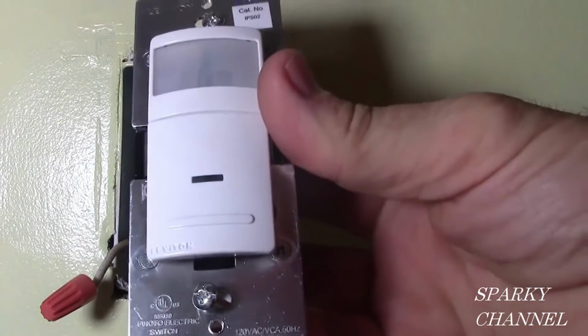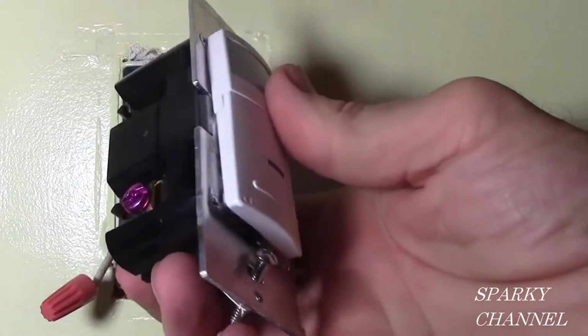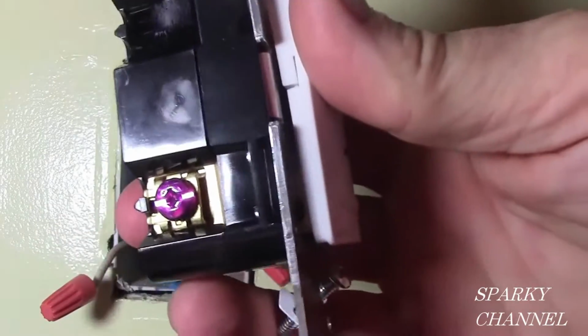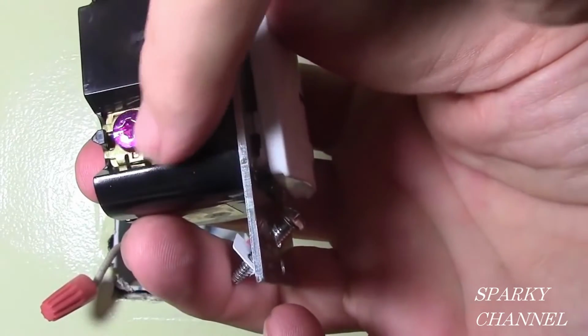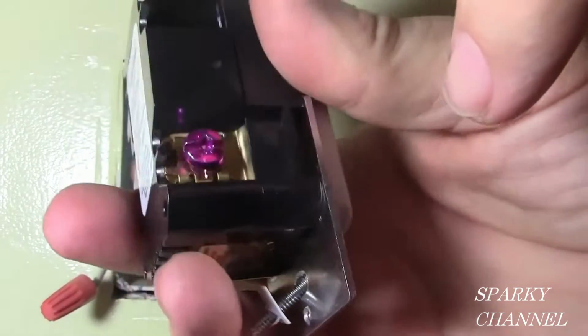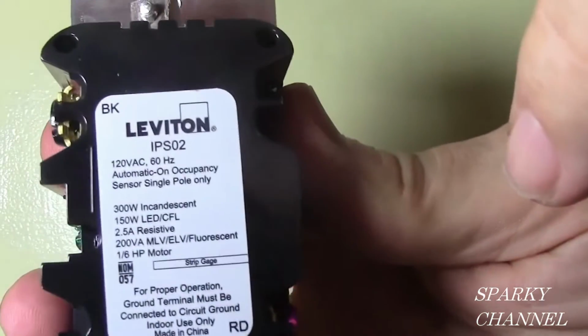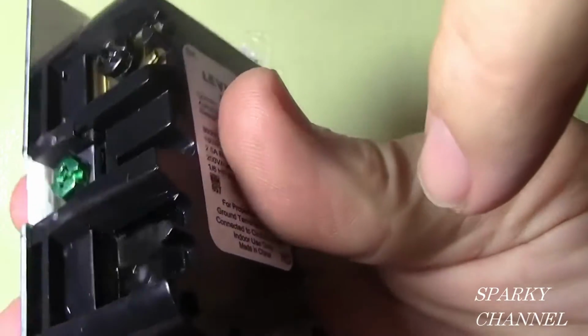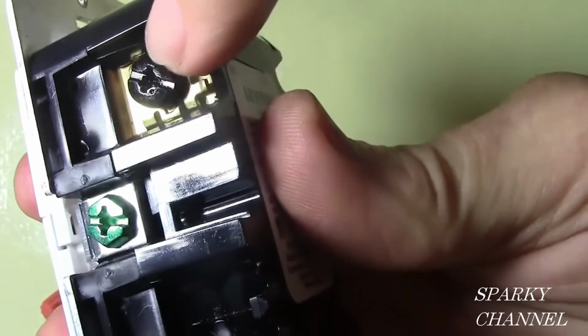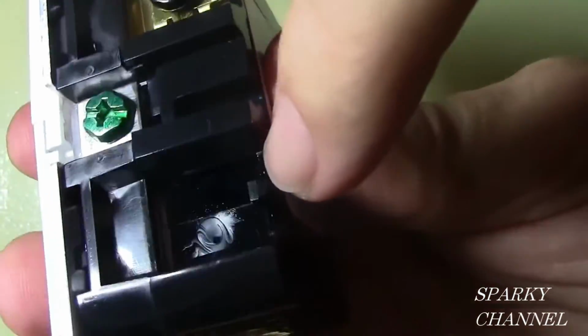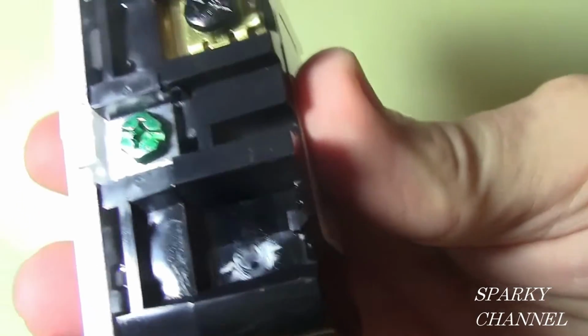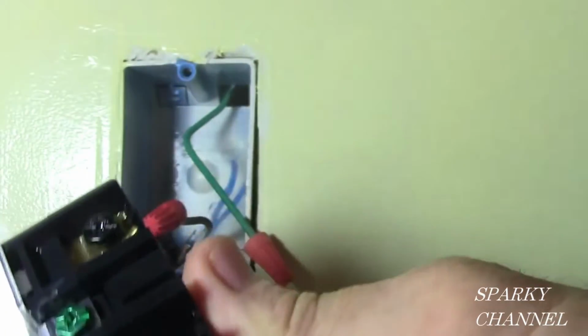Now here is the Leviton IPS02. And notice there's a red screw on one side. That is for your load. That's the load wire. On the other side, we have a black screw. That is for your line wire. And a green screw, which is for your ground.